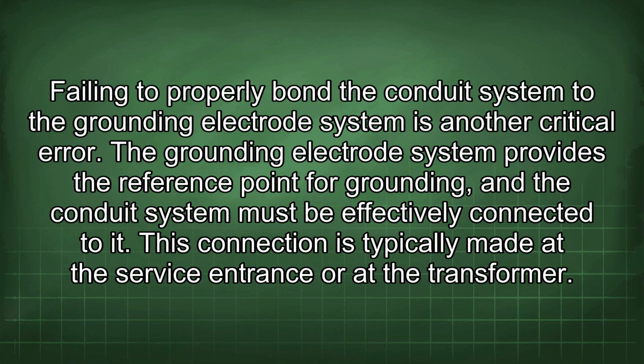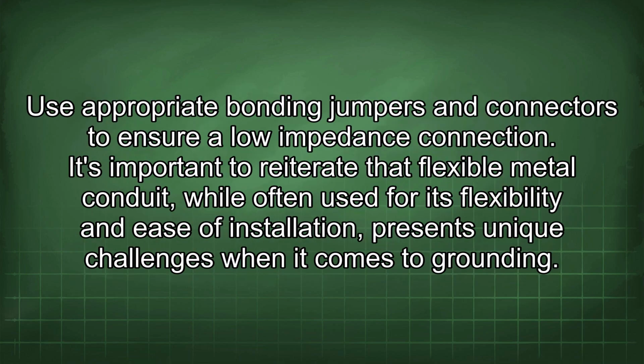Failing to properly bond the conduit system to the grounding electrode system is another critical error. The grounding electrode system provides the reference point for grounding, and the conduit system must be effectively connected to it. This connection is typically made at the service entrance or at the transformer. Use appropriate bonding jumpers and connectors to ensure a low impedance connection.